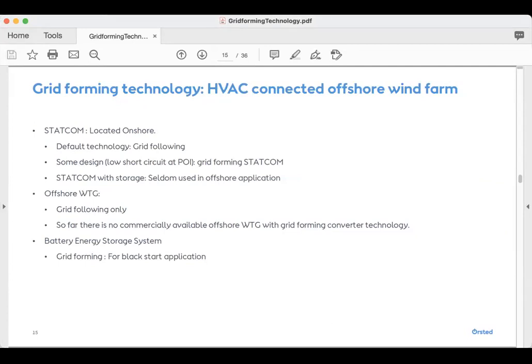Again, from a grid forming technology perspective, the STATCOMs are generally located onshore. We've had STATCOM with grid forming capabilities, again just for low short circuit at the POI. That's the application where we have used it. From an offshore perspective, so far there's no commercially available offshore wind turbine with grid forming capability. And battery energy storage, we have included in some of our designs because there was a request to have black start capability, and the battery energy storage would provide that. If we move to the next slide, please.